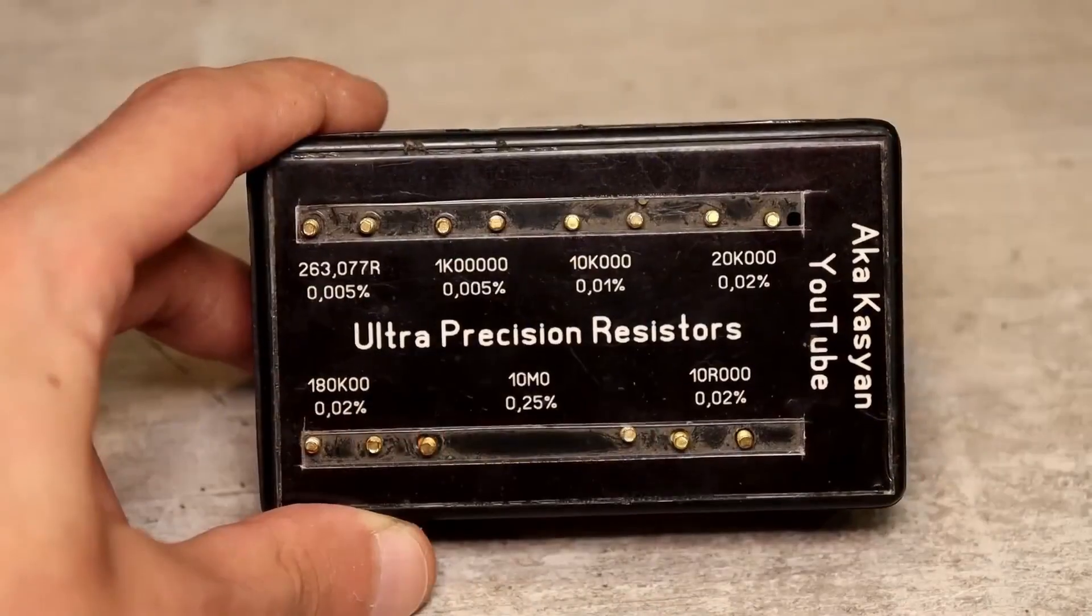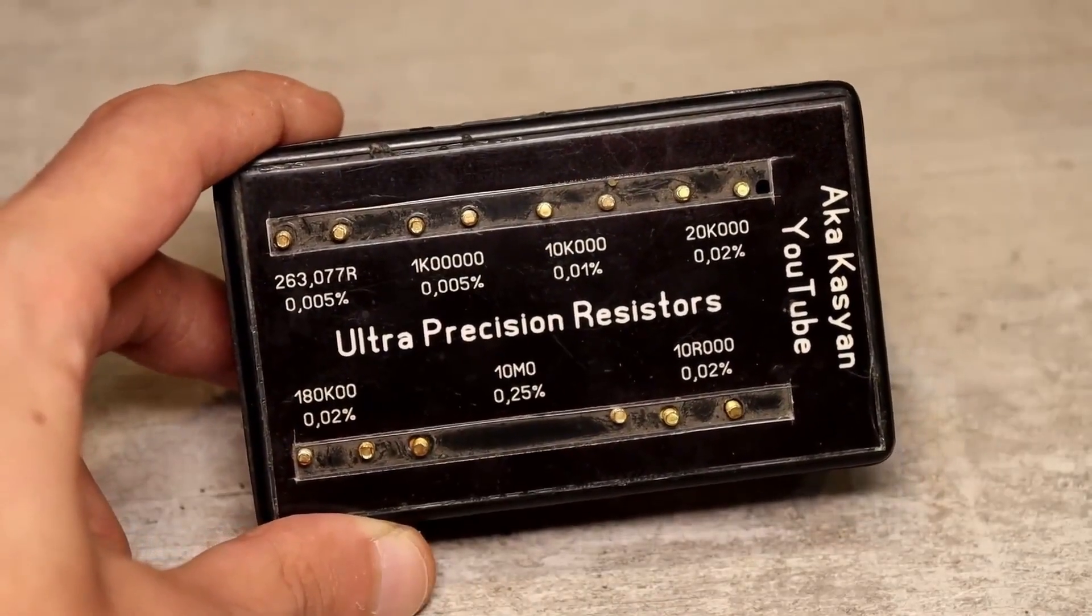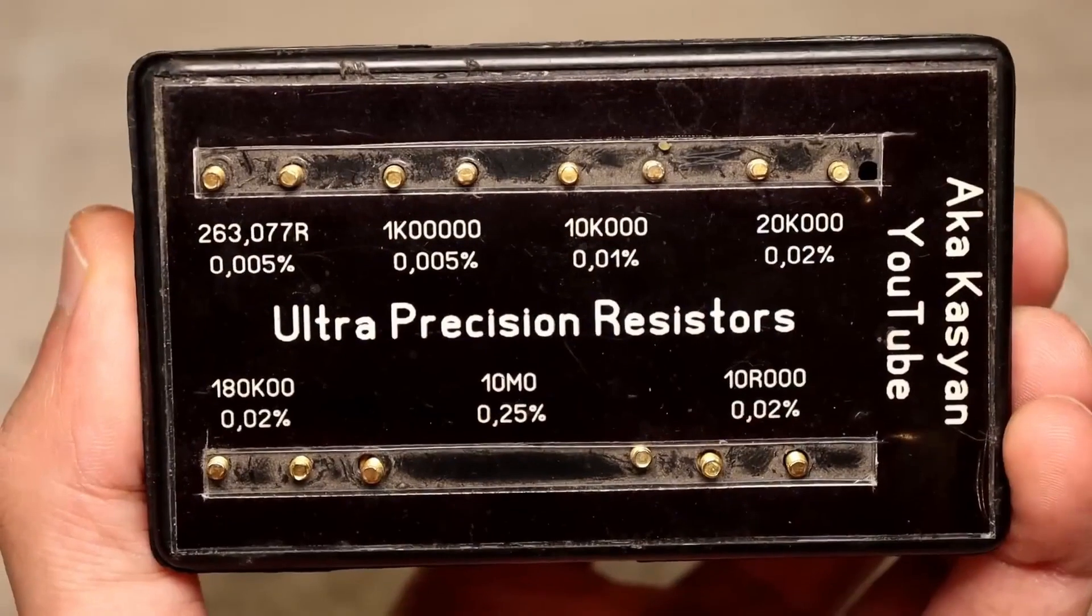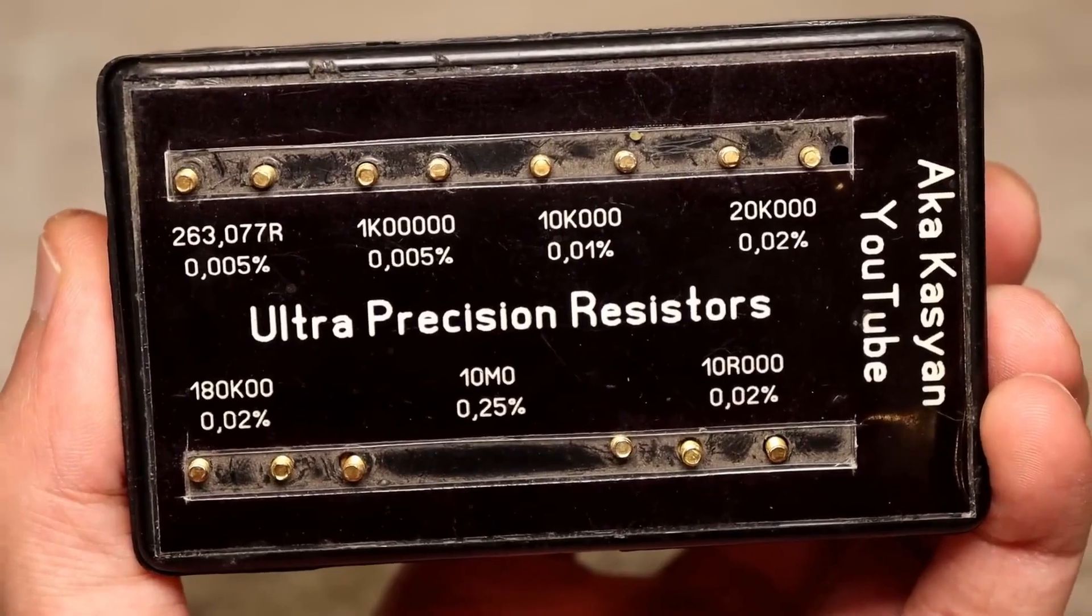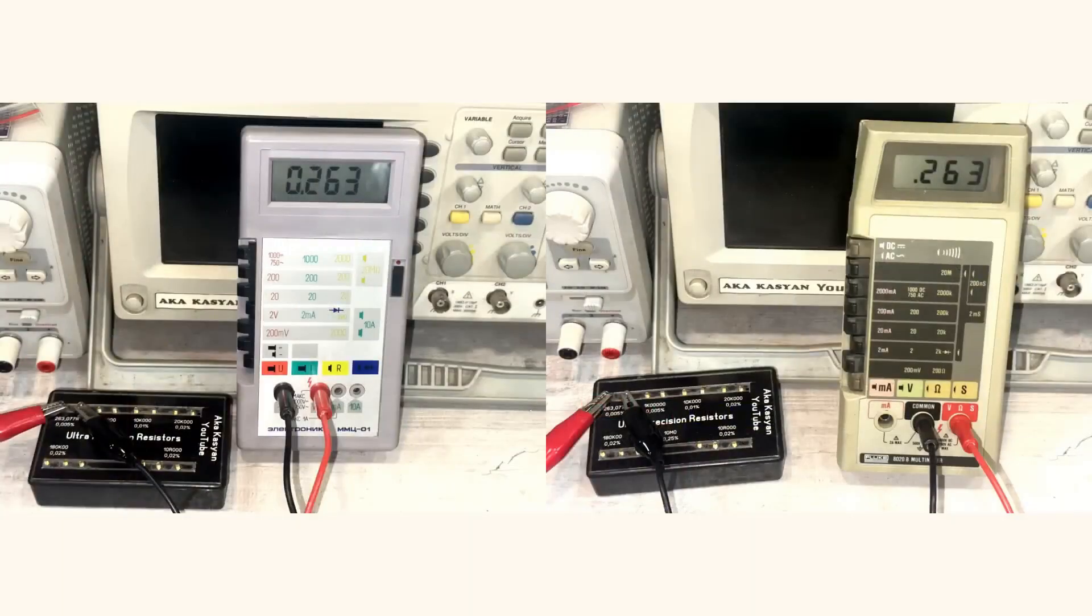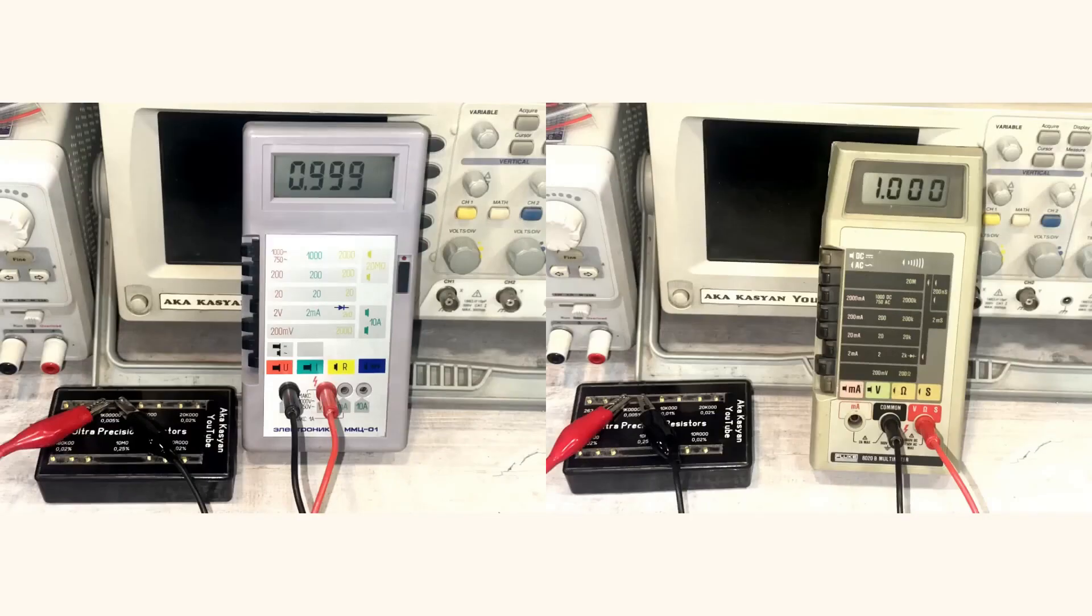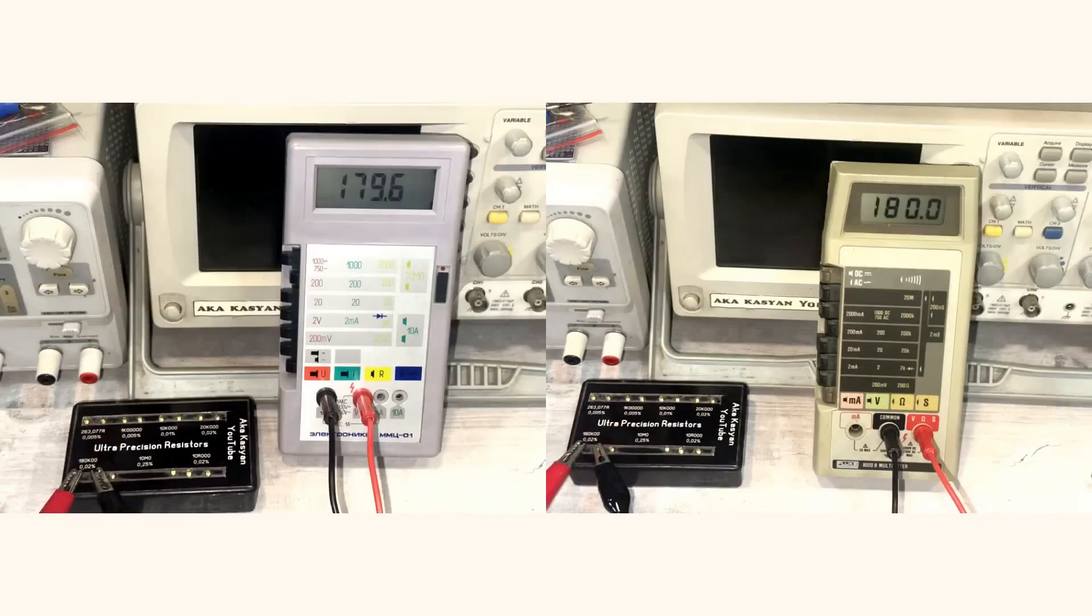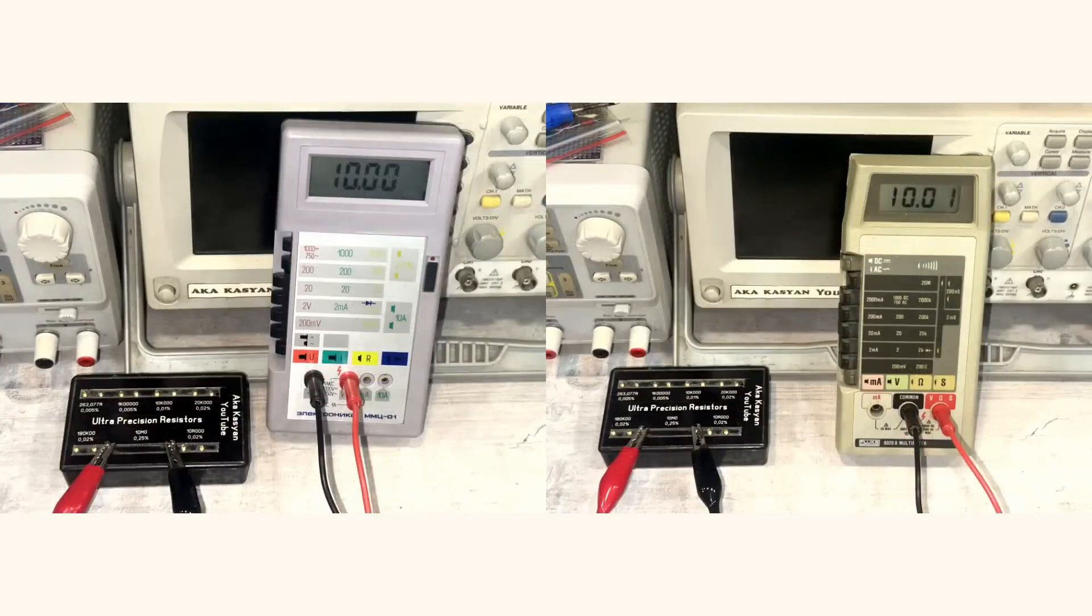Resistance meter. We have this kind of box, inside which are hidden ultra-precise and ultra-stable resistors. The first reference resistance is 10 ohms. Fluke. Electronics MMC 01. 263.077 ohms. 1 kiloohm. 10 kiloohms. 180 kiloohms. 10 megohms.